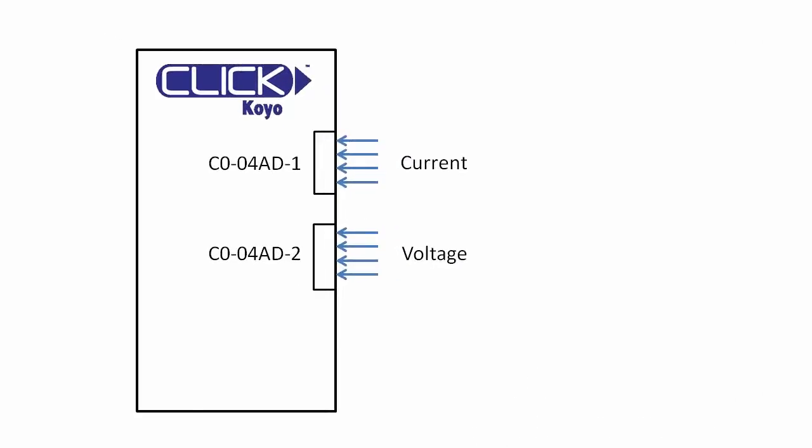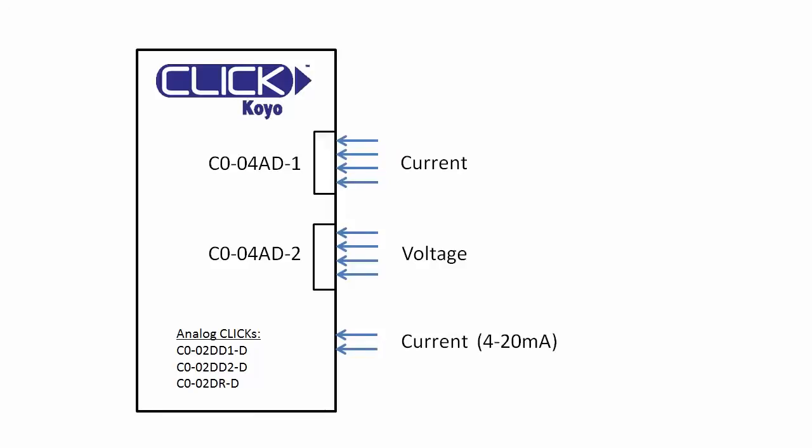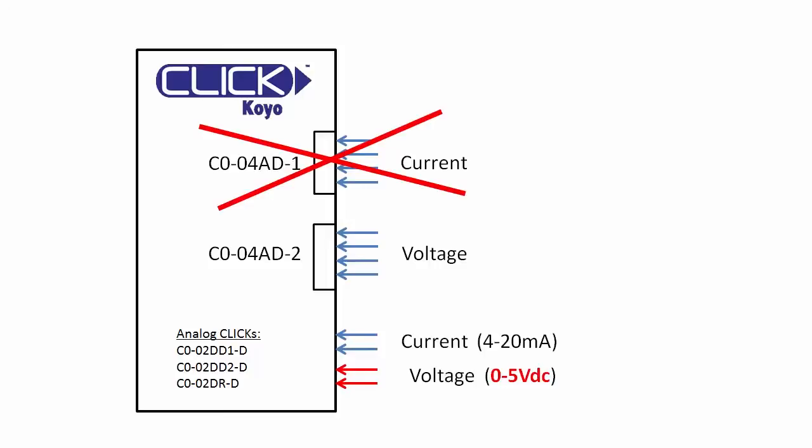Now as a side note, could we have used one of the analog click PLCs here? Sure, they come with two analog current inputs and two analog voltage inputs. The only issue is the voltage inputs are 0 to 5 volts, but our sensors are 0 to 10 volts. So for this example we could only eliminate the extra current module.